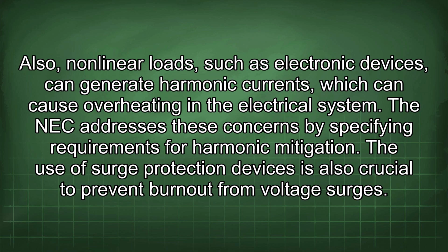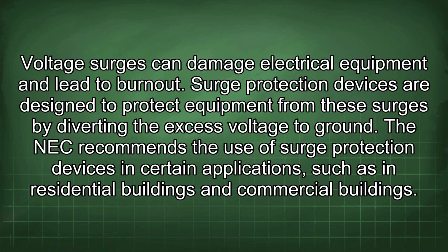The use of surge protection devices is also crucial to prevent burnout from voltage surges. Voltage surges can damage electrical equipment and lead to burnout. Surge protection devices are designed to protect equipment from these surges by diverting the excess voltage to ground. The NEC recommends the use of surge protection devices in certain applications, such as in residential buildings and commercial buildings.